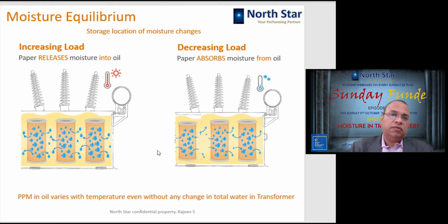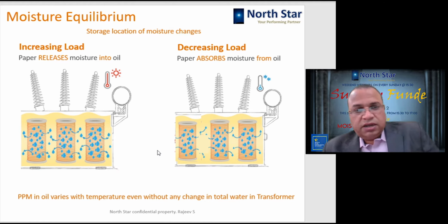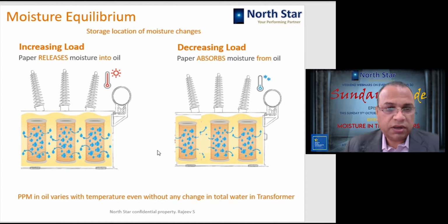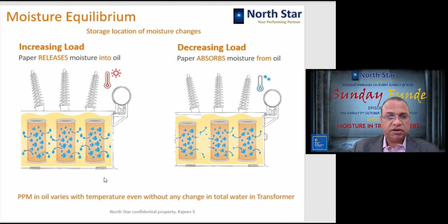Let us see the behavior of the moisture inside the transformer. It is not a static situation. When water is inside, it does not remain in one position. It keeps getting exchanged between the solid, that is paper, and the liquid, that is oil. When the transformer is hot, when the load is high, the moisture is released by the paper. You can see in this figure it is being released by the paper into the oil. So at high temperature or higher loads, the moisture concentration in the oil will be comparatively higher.